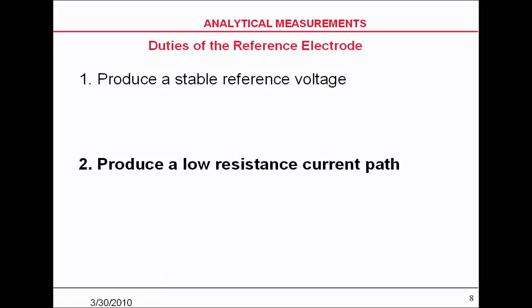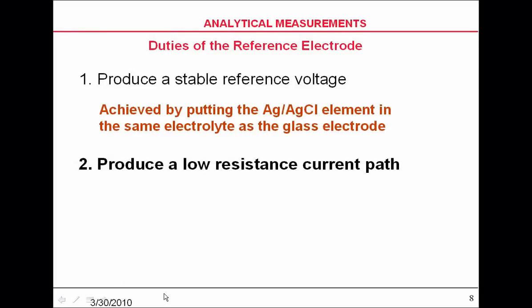What's the functions of the reference electrode? One is to produce a stable reference voltage, and the other is to produce a low resistance current path. We produce a stable reference voltage by using a silver-silver chloride element in the same electrolyte as what's in the glass electrode. We produce a low resistance current path by keeping your liquid junction clean.